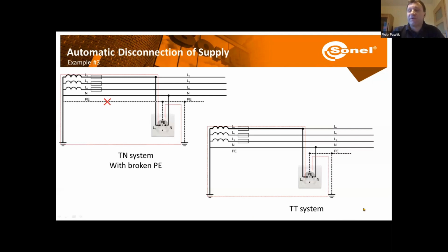And finally, third example, where will be lower value of measured fault loop impedance in case of a TN network, but here we have a broken PE wire or a TT system. Well, in this situation, measured values will be about the same. However, it is important to us, to test technicians, to know what kind of system we are measuring, because in case of a TT system, evaluation will be positive. But in case of a TN system, here we would know that our results are just too high and that our PE wire is broken at some point. And that's why the loop is closing through the actual earth instead of the wire that goes through the walls.